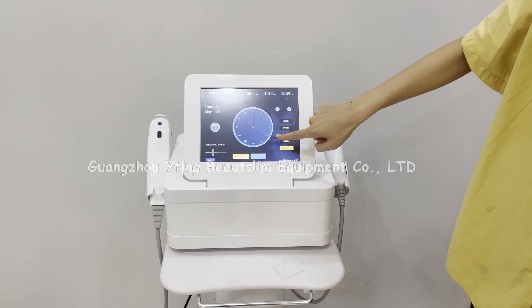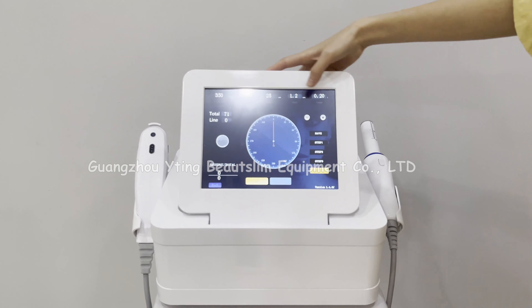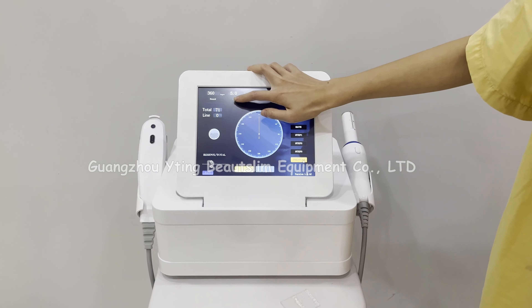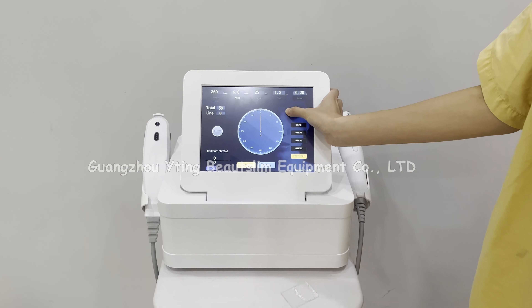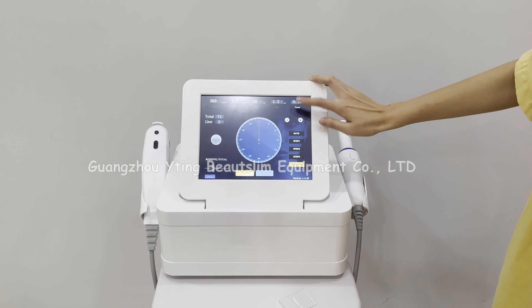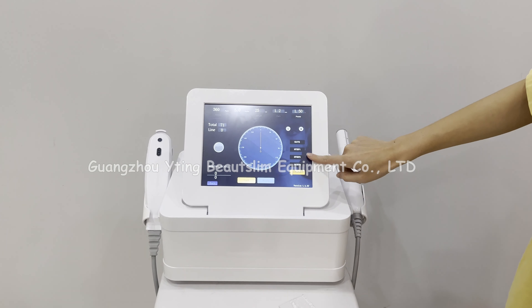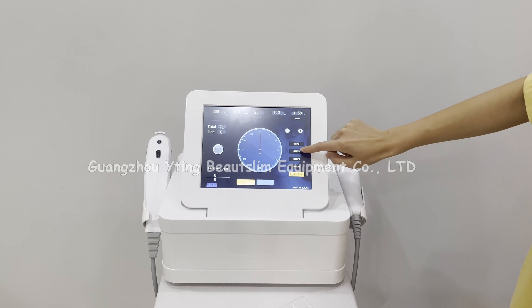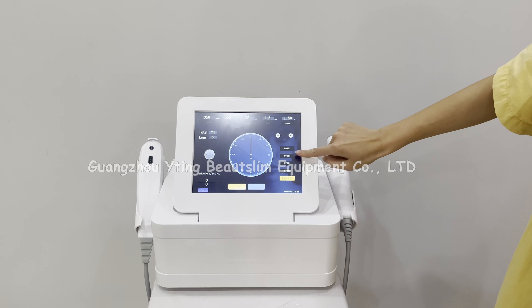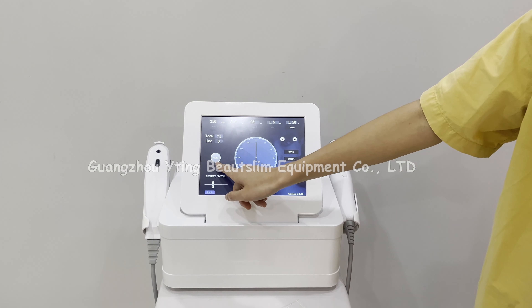Click here to choose the HIFU handle. You can see on the screen: this is the round degree setting, this is the angle of each shot, this is the length, this is the pitch, and this is the power setting. This is for saving different clients' data — click save and the data will be saved for the first client. This is auto mode; if you choose auto mode, the handle will work after one shot.